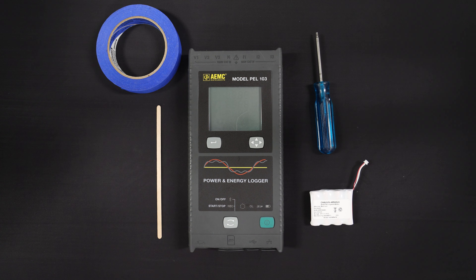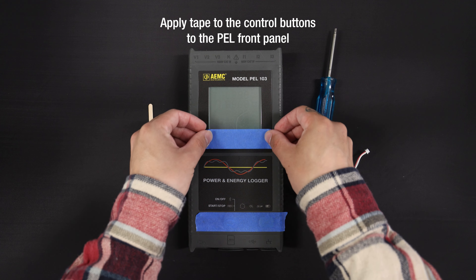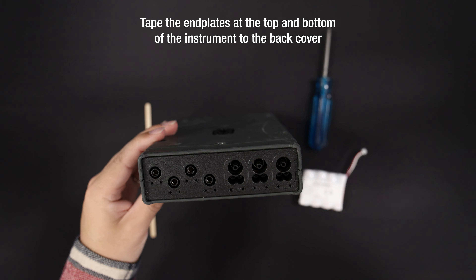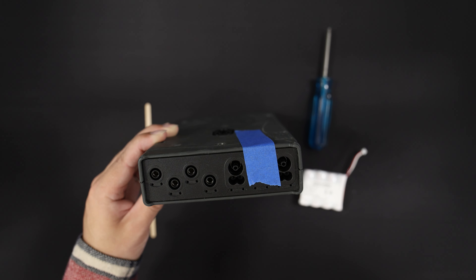To replace the battery pack in the PEL 102 or 103, disconnect the instrument from all electrical sources and sensor probes, then follow these steps. Start by applying tape to the control buttons on the PEL front panel to keep them in place when removing the front cover from the back cover. Next, tape the end plates at the top and bottom of the instrument to the back cover, as shown on the screen, to ensure they stay attached when the front cover is removed.